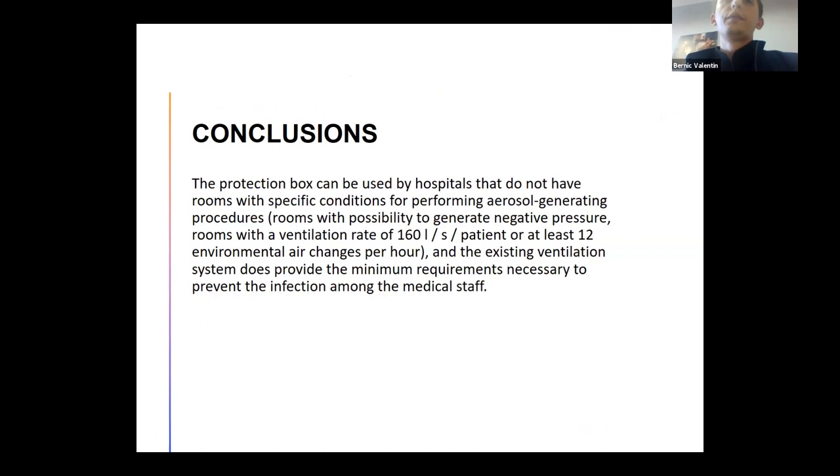In conclusion, the protective box can be used by hospitals that do not have rooms with specific conditions for performing aerosol-generating procedures — including rooms with the possibility to generate negative pressure, rooms with a ventilation rate of 160 liters per second per patient, or at least 12 air changes per hour. The existing ventilation system provides the minimum required airflow necessary to prevent infection among medical staff.